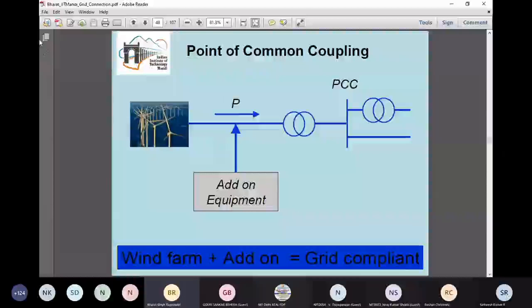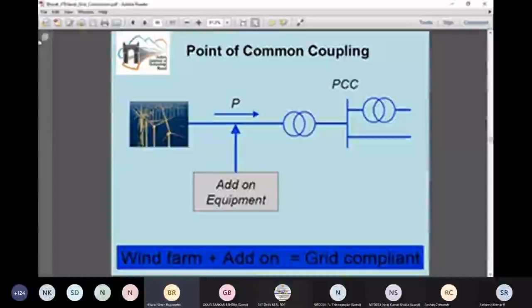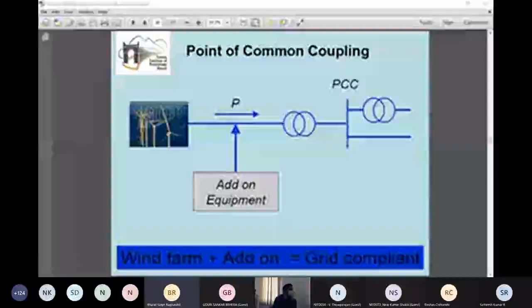Finally, all these grid connection requirements are expected to be met at a point known as the point of common coupling. The right-hand side of this point is developed by the state electricity boards, where the infrastructure belongs to the state, and the left-hand side is mostly the renewable energy developer, the wind farm or solar farm developer. The point of common coupling is also a debatable point and depends on the state. Different states have different definitions of it, and it is required that the definition be the same across the country. Every grid connection requirement is expected to be met at the point of common coupling, and energy metering also happens at the PCC.